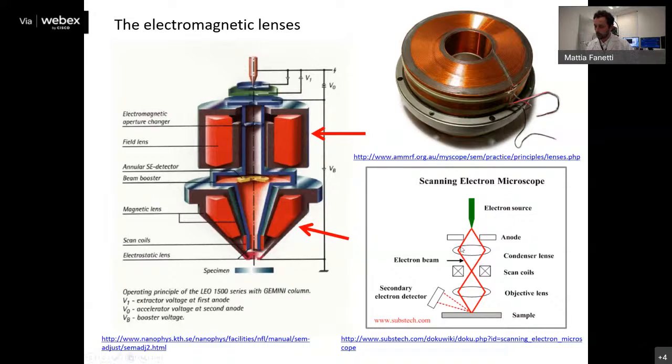So how does it work? The electrons which are incident in the lens hole with higher angles, so that are more deflected from the axis, will be deflected more than the electrons which pass closer to the center. And in this way, I have a focusing effect. Okay, so I can collect all the electrons in a point at the focal length.